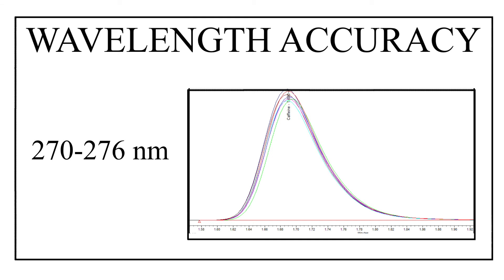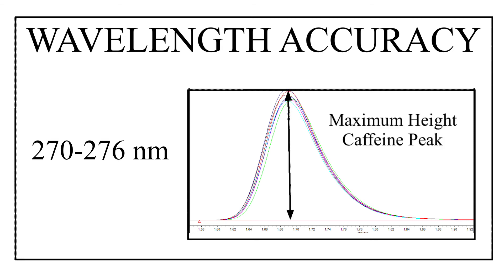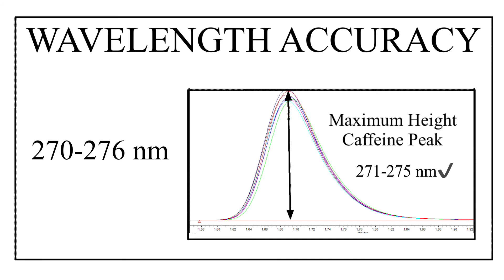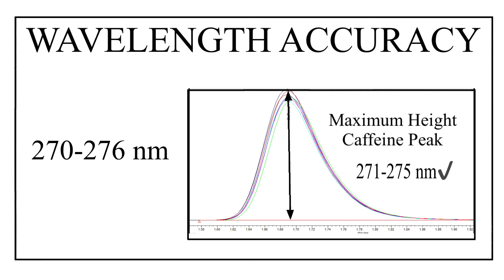Finally, the caffeine peak obtained from the wavelength range 270 to 276 nanometers is evaluated for maximum height, and it should be between 271 and 275 nanometers. This concludes the wavelength accuracy test evaluation.